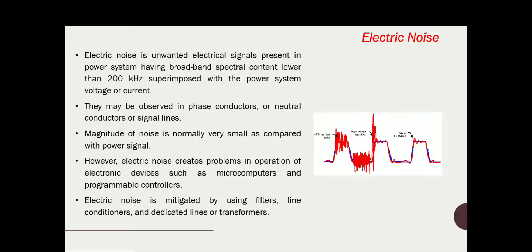Electrical noise signals are unwanted in your electrical signal but are present without any intention. They may be observed in phase conductors, neutral conductors, or signal lines. The magnitude of the noise is normally very small compared with the power signal. However, electrical noise creates problems in operation of electronic devices such as microcomputers and programmable controllers. Electric noise is mitigated by using filters, line conditioners, and dedicated lines or transformers.